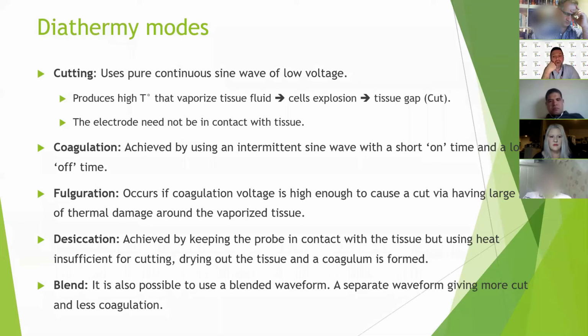Now, let's talk about modes. We mentioned the cutting and coagulation. There are other modes, and it depends on the electricity passing through and how they do. So the cutting mode is when you have a pure continuous sine wave, all of them are continuous sine waves, but here you have continuous and low voltage. And that produces high temperature, vaporizing the tissue, causes cell explosion, and then a gap appears. So that's the cut. And here you don't have to have full contact with the tissue because it's the heat. It's not the electricity.